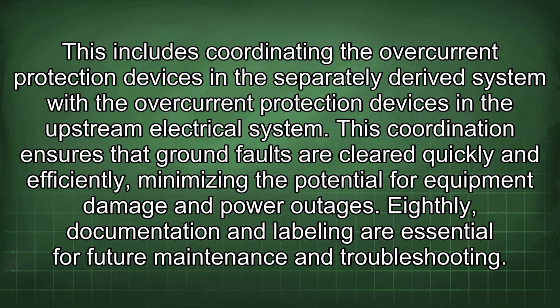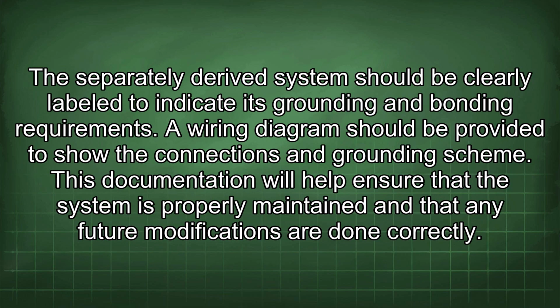Eighthly, documentation and labeling are essential for future maintenance and troubleshooting. The separately derived system should be clearly labeled to indicate its grounding and bonding requirements. A wiring diagram should be provided to show the connections and grounding scheme. This documentation will help ensure that the system is properly maintained and that any future modifications are done correctly.